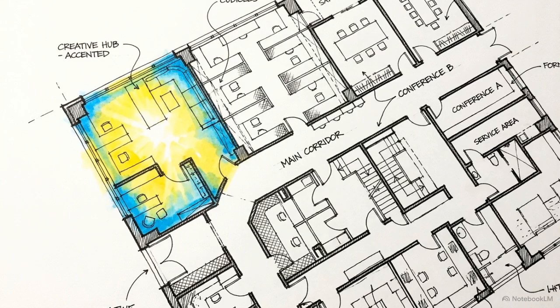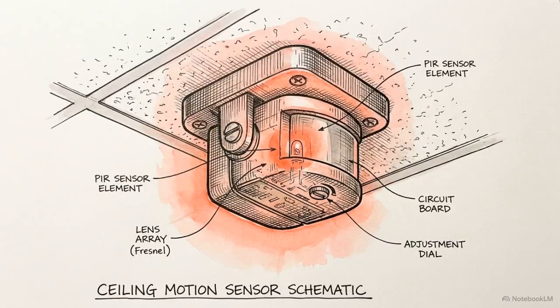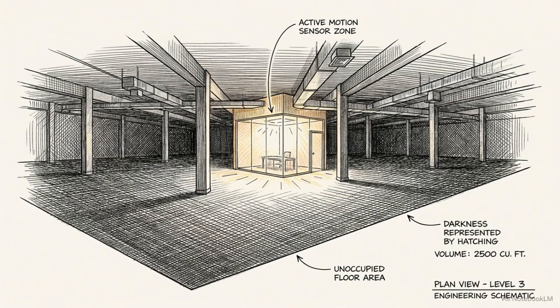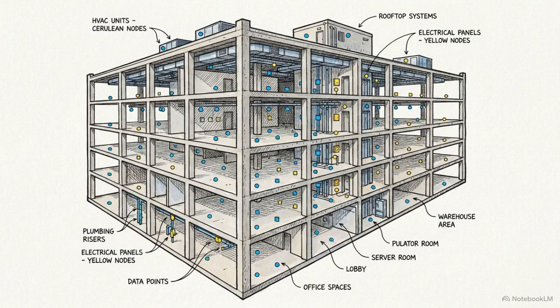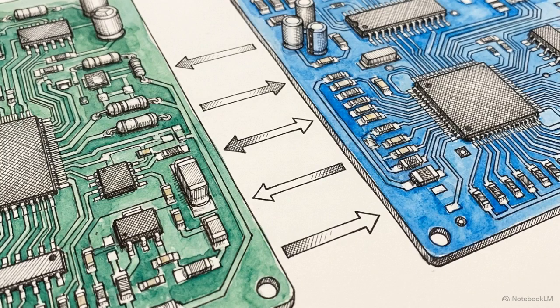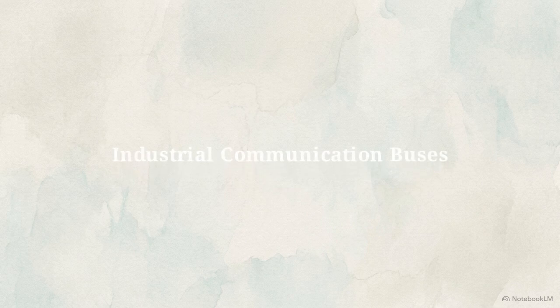Together, these bottom 2 layers form the unthinking reflexes of the building. They react instantly to physical changes, but they have no broader context of what the rest of the facility is doing. A typical commercial building contains hundreds or thousands of these local control loops. So how do disparate controllers pass data to each other? They use specialized industrial communication buses.